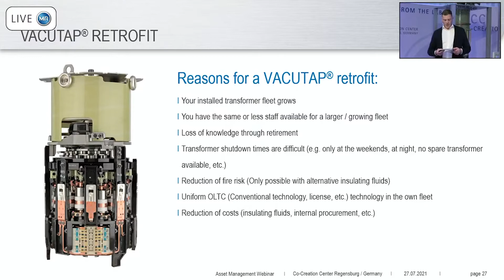Let us compare in detail the OILTAP M with the VacuTap VM. On the left, this is the conventional technology, the OILTAP M, and on the right, the VacuTap VM. You see that the lifetime of this DSI is already 400,000 operations higher, so the lifetime of the M is 800,000. Compared to the VM, it is 1.2 million. The important thing is that the maintenance must just be performed at 300,000 tap change operations. This is a very high number, and for sure you reach that just when you operate your transformer in harsh conditions. I think, or you for sure know that for the most network application, this tap changer is then completely maintenance free. The VM offers also the possibility to perform a dissolved gas analysis DGA, and of course some more benefits which you can see in this overview.